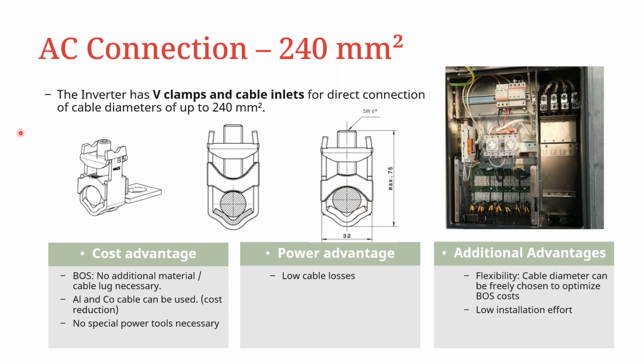cable cross-section. So the cost advantage of having these V clamps integrated into the inverter, of course, like we said, no additional materials, cable lugs and stuff like that are required. It's compatible with both aluminum as well as copper cables. So therefore, you can choose which cables are most cost-friendly to you. And then, of course, no special tools are required for connection. So just an Allen key is enough for you to be able to apply the right torque for that particular V clamp. So the power advantages, of course, are low cable losses.